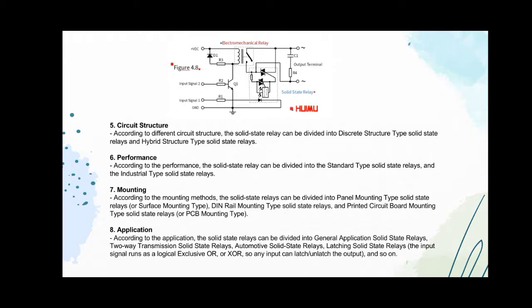So number 6, the performance. According to the performance, the solid-state relay can be divided into standard type solid-state relays and industrial type solid-state relays. The rated current of the standard solid-state relay is generally 10A to 120A, and the rated current of the industrial solid-state relay is relatively large, from 60A to 2000A or larger. Therefore, the industrial SSR can meet the strict requirements of the industrial environment and industrial machinery.